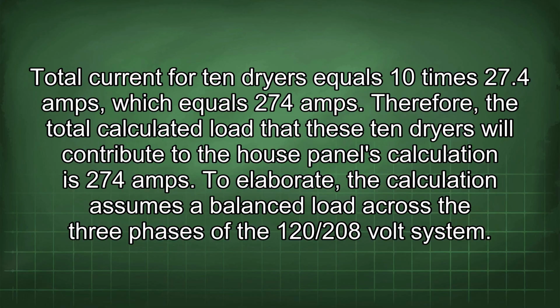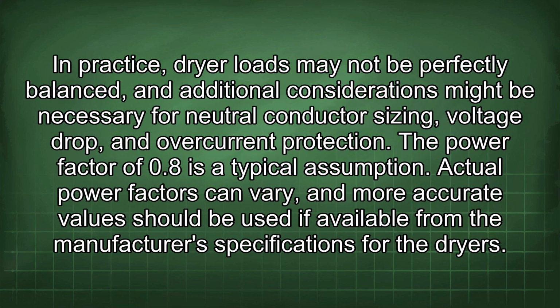To elaborate, the calculation assumes a balanced load across the three phases of the 120/208 volt system. In practice, dryer loads may not be perfectly balanced, and additional considerations might be necessary for neutral conductor sizing, voltage drop, and overcurrent protection. The power factor of 0.8 is a typical assumption. Actual power factors can vary, and more accurate values should be used if available from the manufacturer's specifications for the dryers.